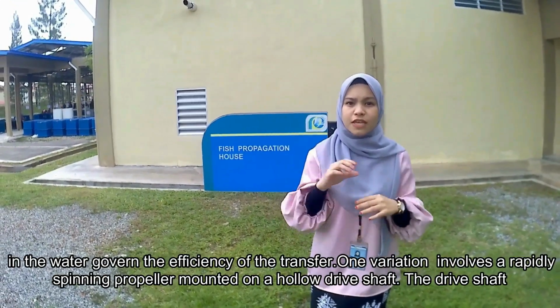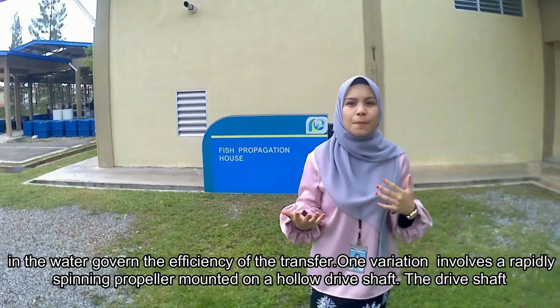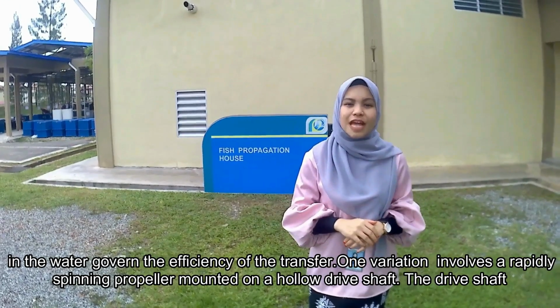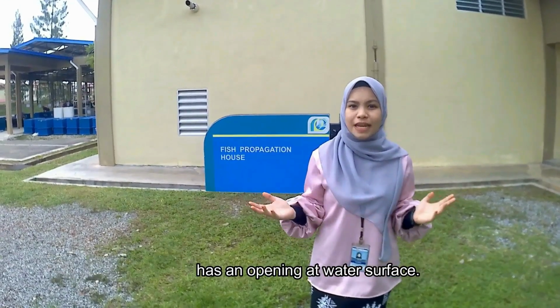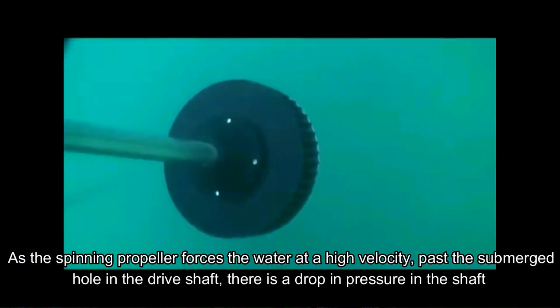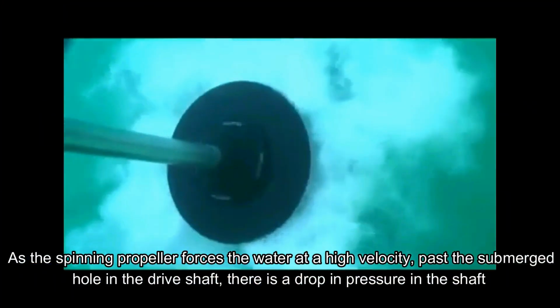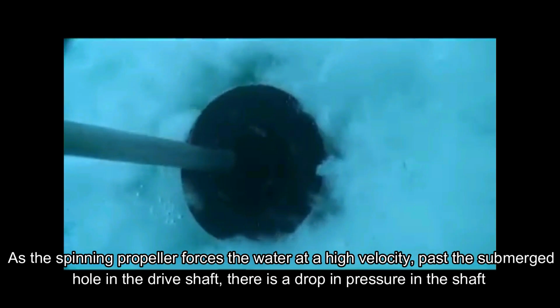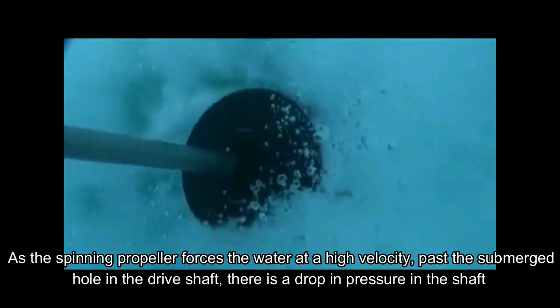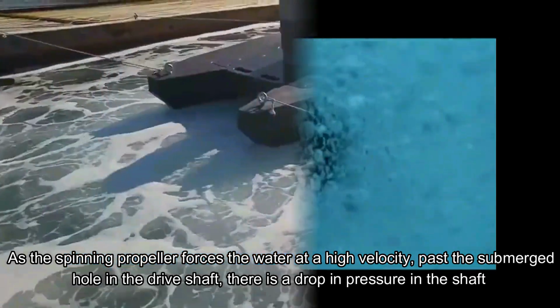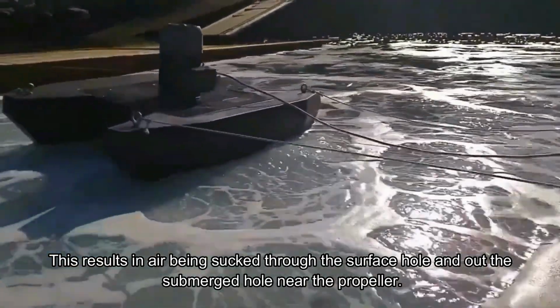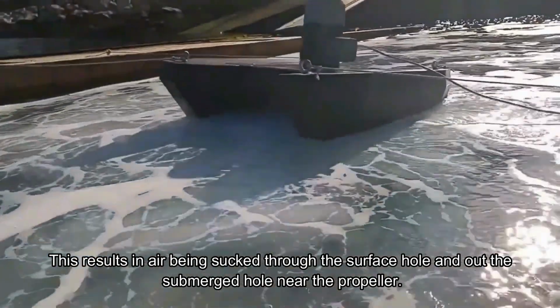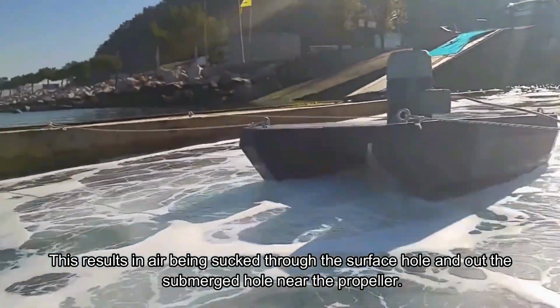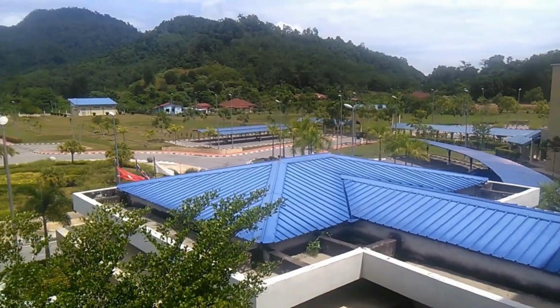One variation involves a rapidly spinning propeller mounted on a hollow drive shaft. The drive shaft has an opening at the water surface as the spinning propeller forces the water at a high velocity past the submerged hole in the drive shaft. There is a drop in pressure in the shaft. This results in air being sucked through the surface hole and out the submerged hole near the propeller.